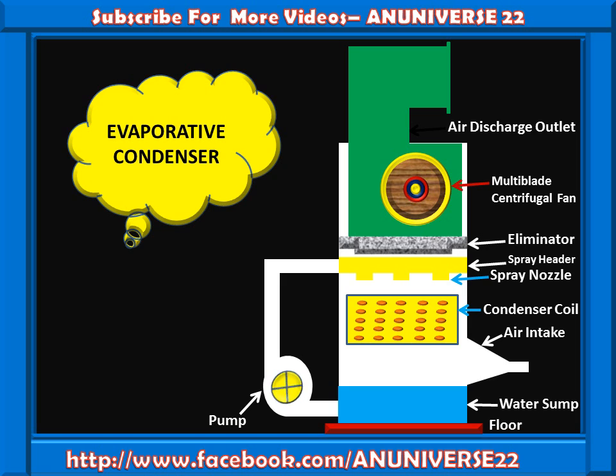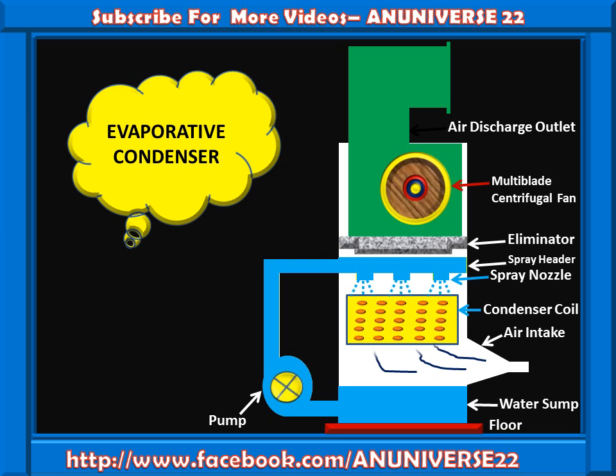When pump starts, then water is pumped from the sump of the evaporative condenser and it is delivered to the spray header, and with the help of spray nozzle it is sprayed over the condenser coil. At the same time, the centrifugal fan draws the air from bottom side of the condenser and discharges it out at the top of the condenser.